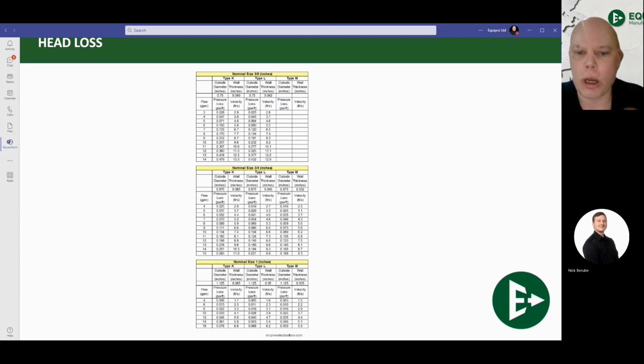So let's just start at the top because it's nice and easy. It's a really easy one to read. Let's start at the very top one. This is type K copper, 5/8 of an inch. When we move 3 GPM through 5/8 inch type K copper, we get 0.026 psi per foot pressure loss.